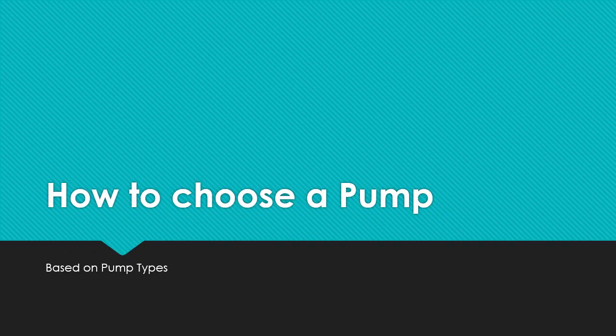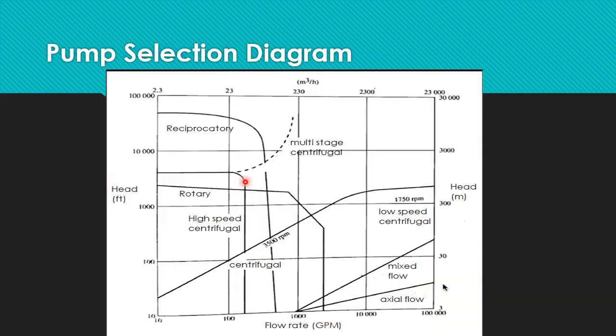So how to choose a pump based on the pump types? This is the general pump selection diagram, which is based on head and flow rate. This is head given in feet, and flow rate given in gallons per minute. This is also head given in meters and flow rate given in cubic meters per hour. If you need a high flow rate and a low head, you will choose axial flow, and similarly if you want a high head and low flow rate pump, you will choose a reciprocating pump. Mostly centrifugal pumps are used in the industries.